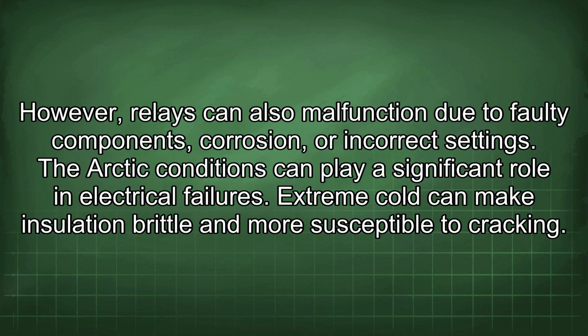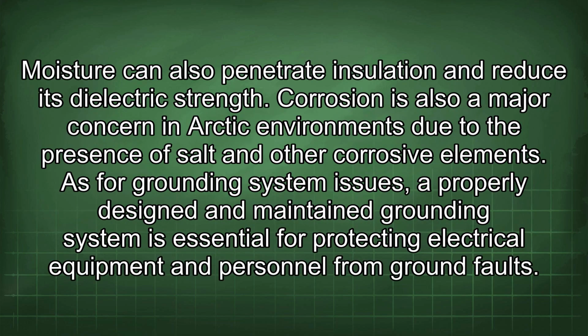The Arctic conditions can play a significant role in electrical failures. Extreme cold can make insulation brittle and more susceptible to cracking. Moisture can also penetrate insulation and reduce its dielectric strength. Corrosion is also a major concern in Arctic environments due to the presence of salt and other corrosive elements.